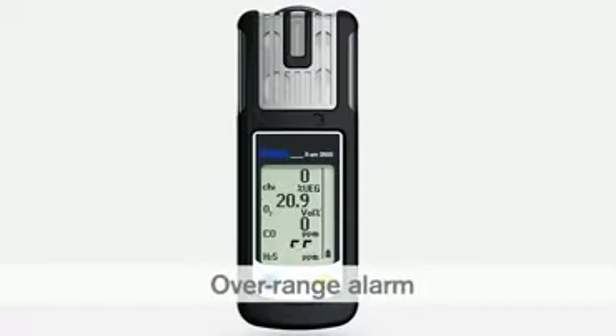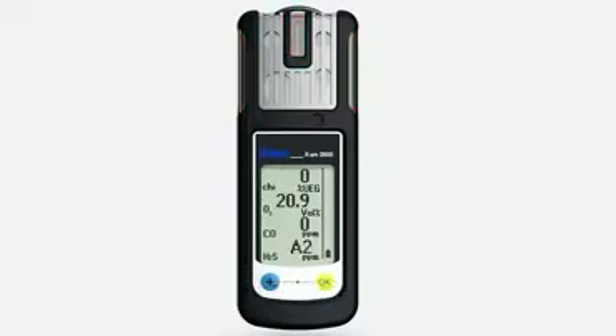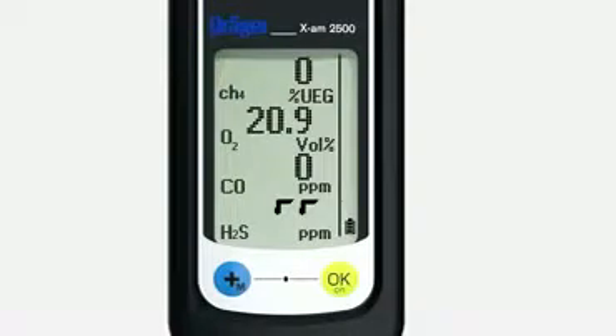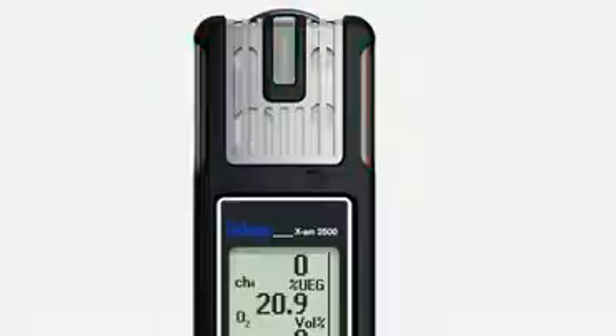An overrange alarm, indicating that the measuring range has been exceeded, is signalled by the audible, visual and vibration alarms. In addition, this symbol alternates in the display with the A2 main alarm symbol. The ambient air contains concentrations exceeding the measuring range of the sensor used. Once again, leave the danger zone immediately. This alarm cannot be acknowledged.